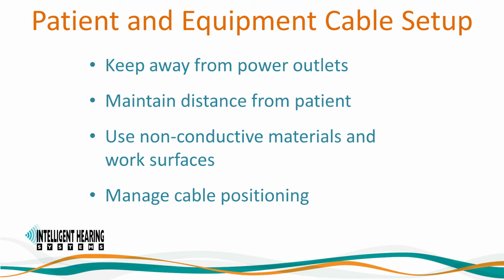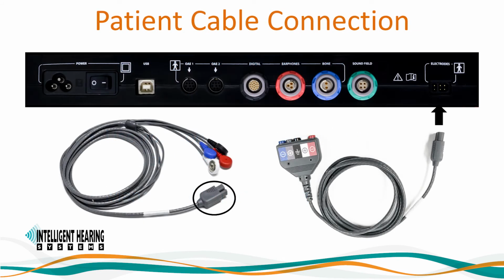The patient cable and leads then run down the neck and to the side shoulder, or down the chest of the patient. When using the Duet platform, make sure the patient cable is pushed in all the way into the patient connector on the Duet box to ensure a solid and proper connection. Loose connections can pick up noise and affect the quality of your recordings. For all OptiAmp devices, ensure that the electrode leads are well connected to the input jacks of the OptiAmp transmitter and not loose. Change the electrode leads to a new set or different type if any interference persists.